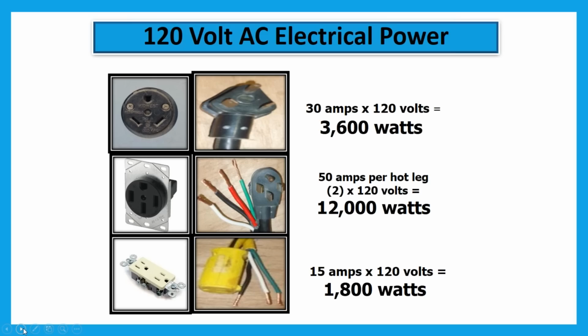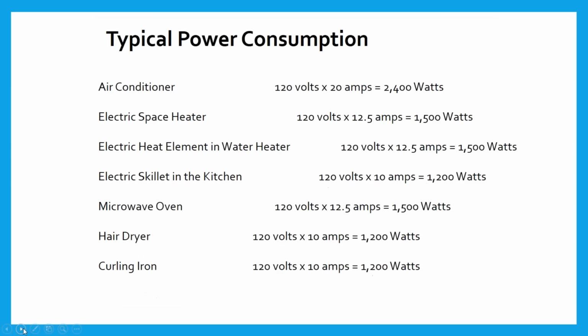Okay, so keep this in mind. 3,600 watts for 30 amp, 12,000 watts for the 50 amp power cord, and we're only looking at 1,800 watts for the extension cord powered stuff. Okay, so let's take a look. Now here's a typical power consumption chart. Your air conditioners. Typically, an air conditioner is going to have a 20 amp circuit breaker, and it's a 120 volt device. So if you take that 120 and multiply by 20, we come up with 2,400 watts.